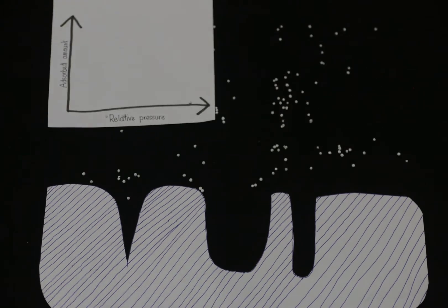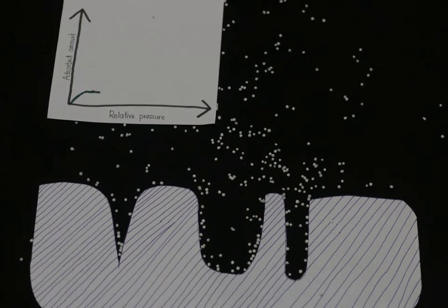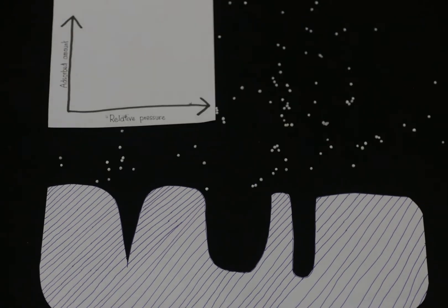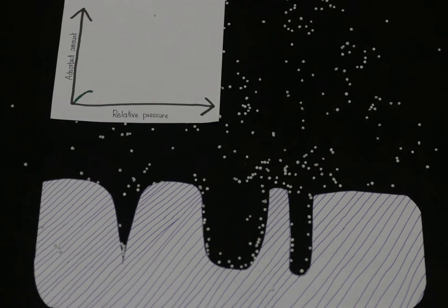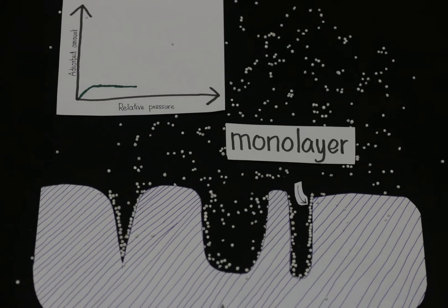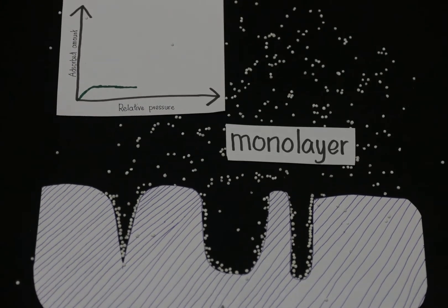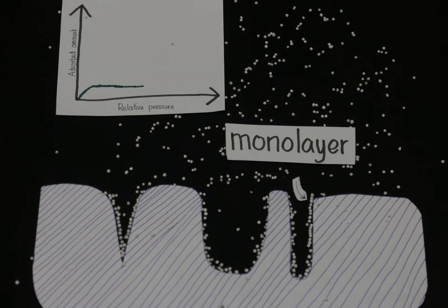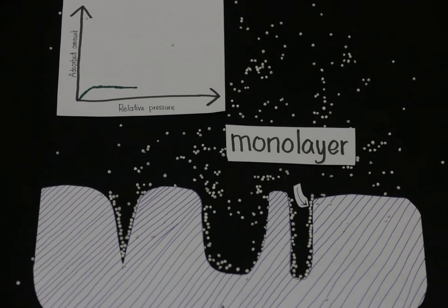The actual measurement of gas sorption begins by exposing the sample to a low pressure of adsorptive gas. As the pressure of gas rises, so does the amount of gas adsorbed at the surface until a monolayer is formed. Observe the isotherm curve as the monolayer forms. It will be used to calculate the BET surface area.